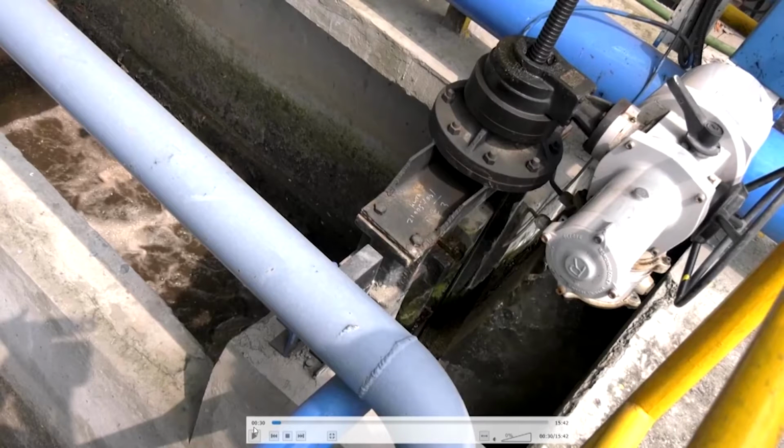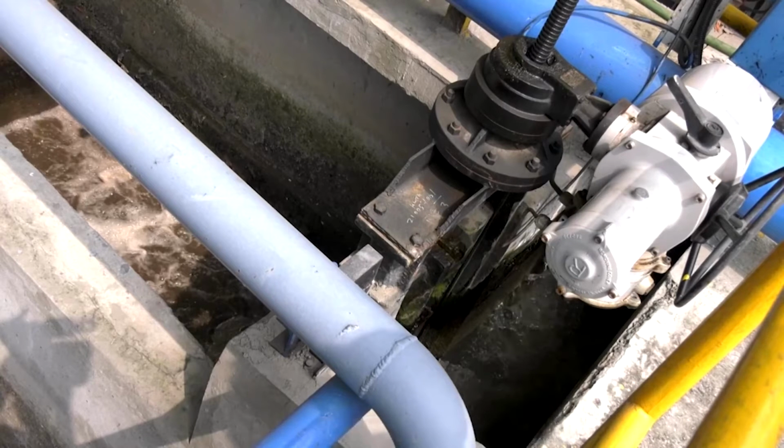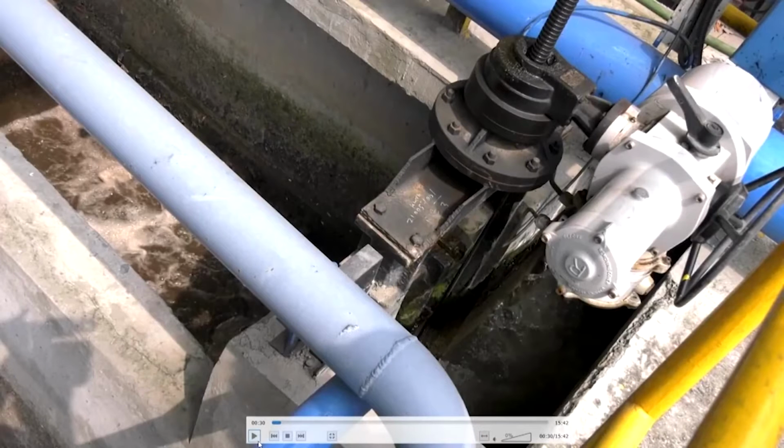We saw that the water is being pumped up to the bioselector tanks, right? Bioselector, as in we want to have high F by M conditions such that the kind of flock forming microbes that we want to thrive will be predominant later or even now, right? So that's what we want to achieve here. So aeration is not going to be continuous here though, for 15 minutes or such, high F by M ratio, let's say, right? So that's what we have.